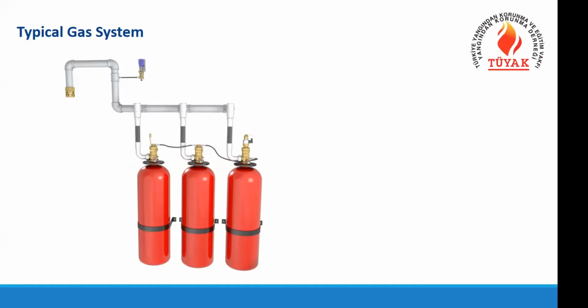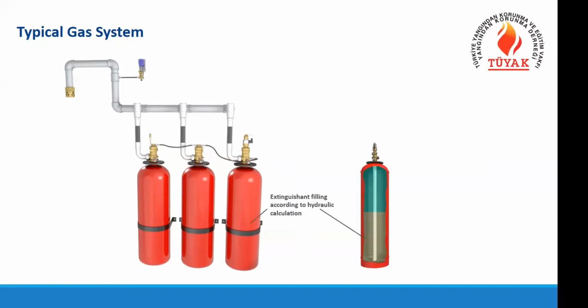A typical gas system has cylinders, a pipe system, and nozzles. And the cylinder has some portion at liquid phase in general, the extinguishing agent. This is in general liquid, but sometimes gas. For the chemical systems, the halocarbon systems, which have a cooling effect, they are in cylinders in liquid condition. And on top of the liquid, we have nitrogen to pressurize this extinguishing agent and direct it to the room with pressure.